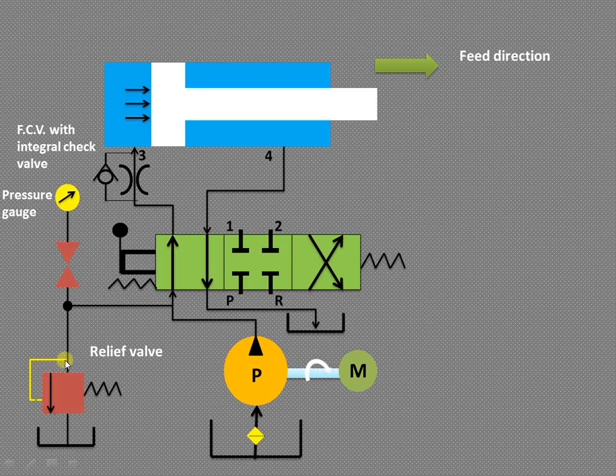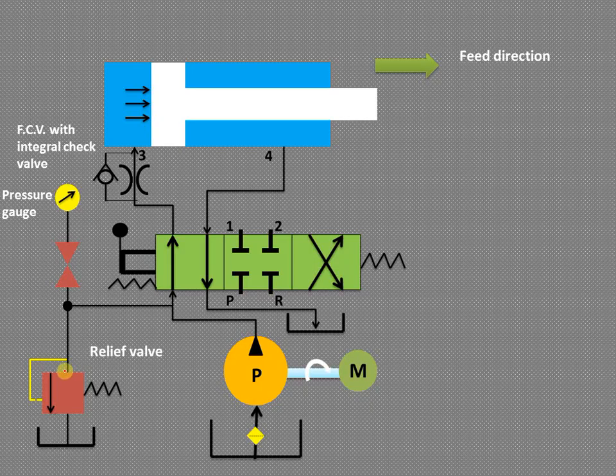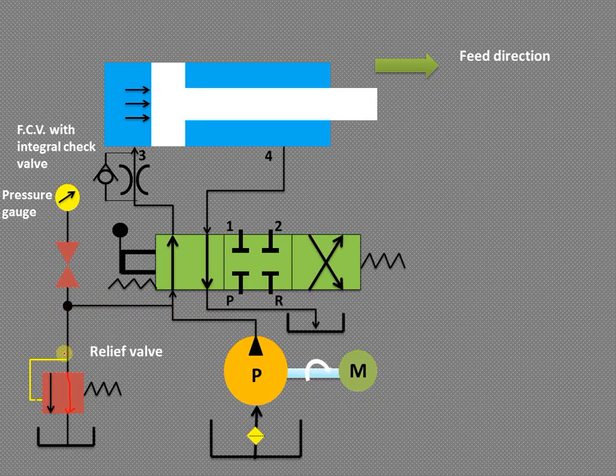If the pressure is excessive compared to the design pressure, the relief valve — which is normally in a closed position as shown — will open. When the pressure exceeds the design value, the arrow shown will shift position, and the liquid flowing from the pump will bypass and go directly back to the receiver, so no further operation will be performed.